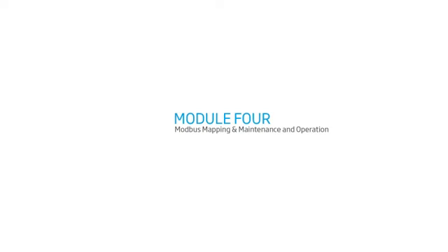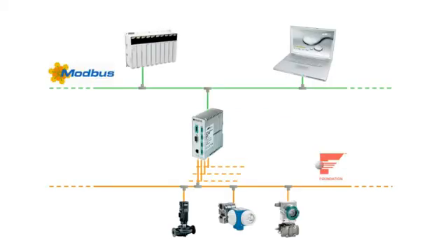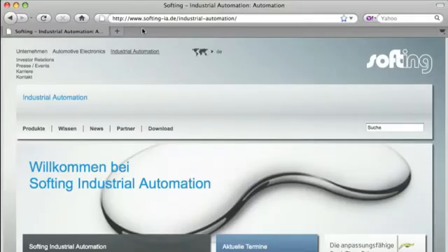One of the use cases for the FIM110FF is to allow traditional control systems access to modern Foundation Fieldbus devices. Typically, traditional control systems do include support for the Modbus communication protocol. The Modbus mapping function is used to associate a process value of a Foundation Fieldbus device value with a Modbus register. The only software you need for the Modbus mapping is a standard internet browser.